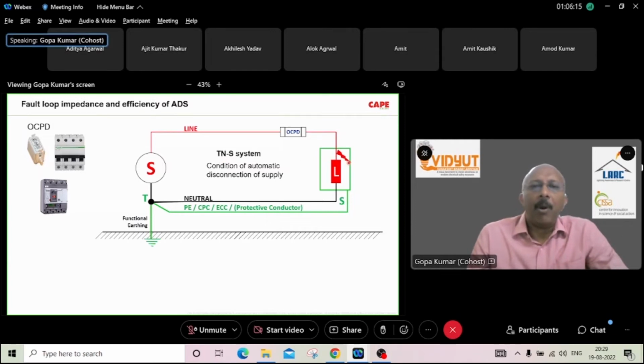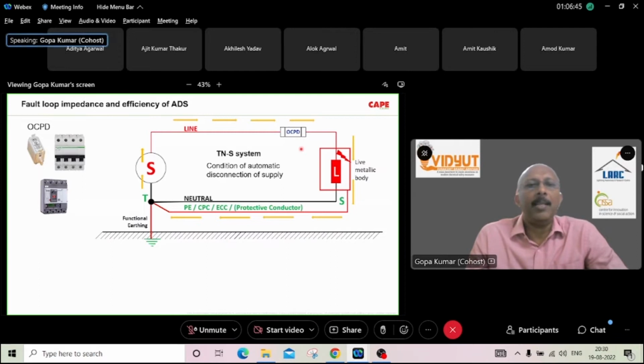Whenever there is a fault in the exposed conductive part of your installation, the fault current will flow through the metallic fault return path, through the source, through the phase conductor, and now you have a closed loop. The electricity is flowing through this closed loop. The impedance of this loop decides the amount of current flowing at that particular time, and the amount of current decides the disconnection time.